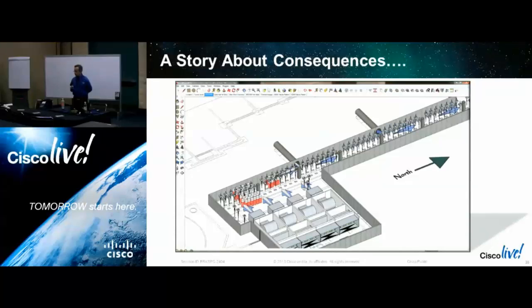They had a problem in terms of the length of rows. They were not uniform. One back of rack was feeding the front of another. They had sensors deployed, but some were not operational, and the software was past end of life and could not be restored. In fact, the server it lived on had died, and they couldn't restore the management software anymore.